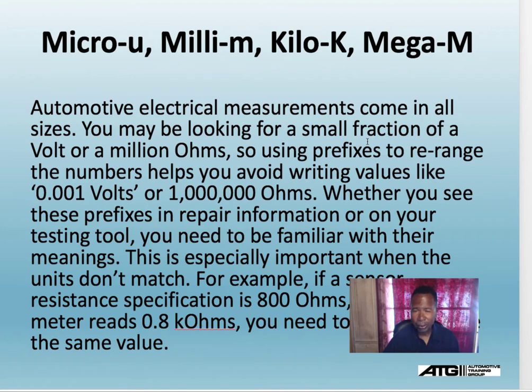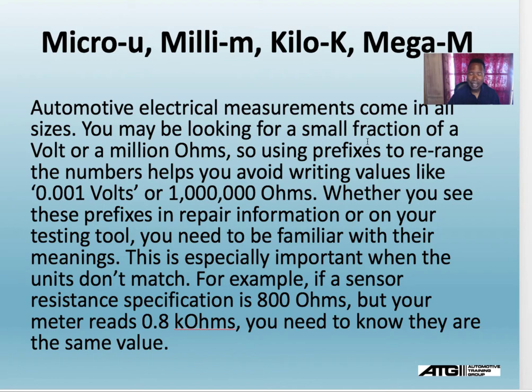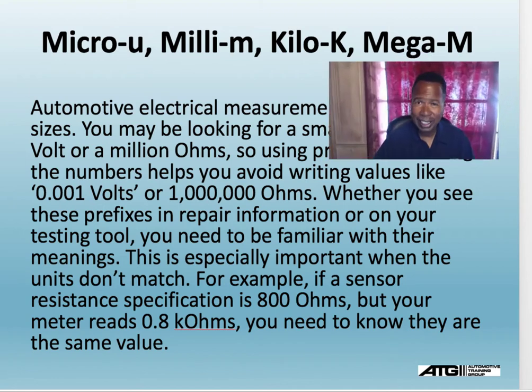This is especially important when the units don't match. For example, if a sensor resistance specification is 800 ohms, but your meter reads 0.8K ohms, remember the K is abbreviation. It's in the thousand place, so you have to move the decimal three places from where it sits to the right. You need to know that they are the same value.